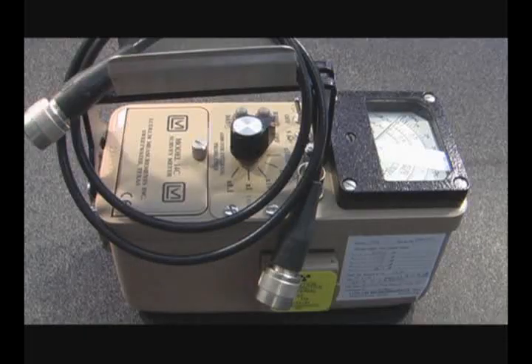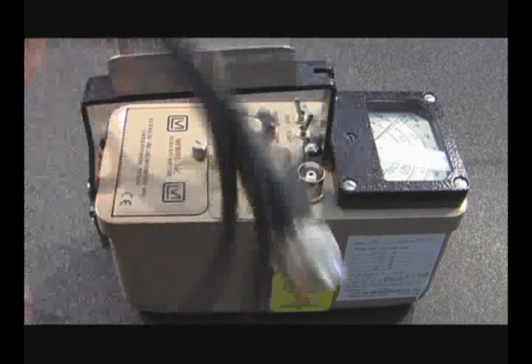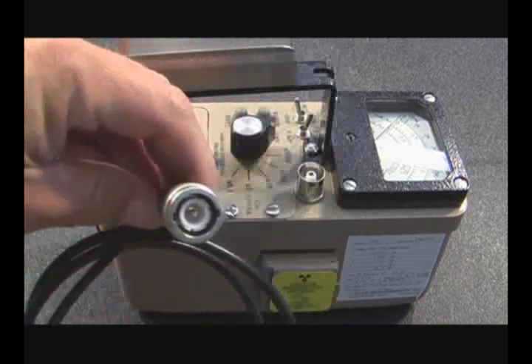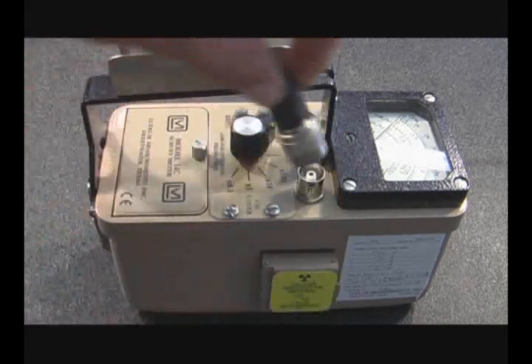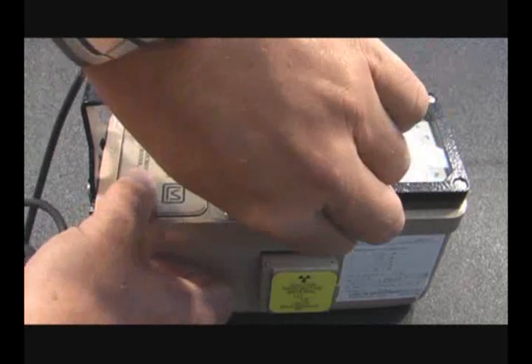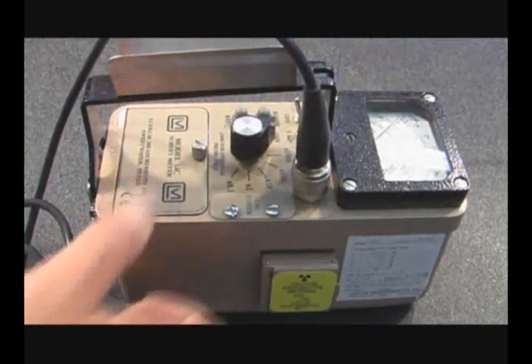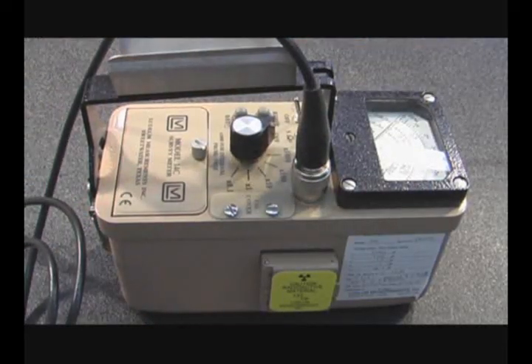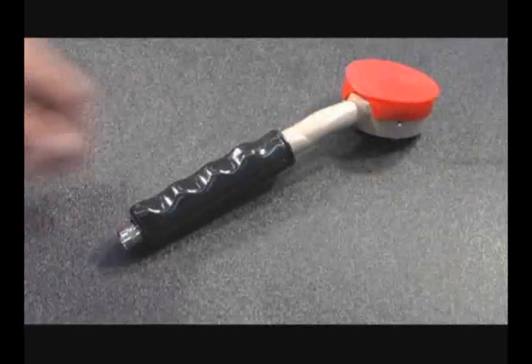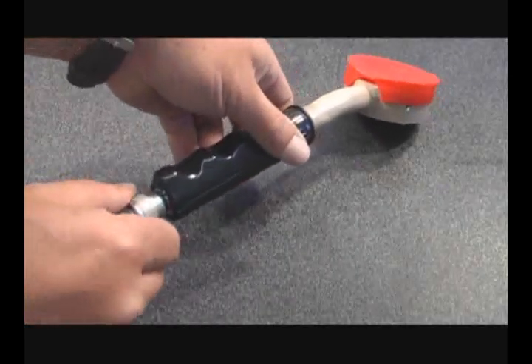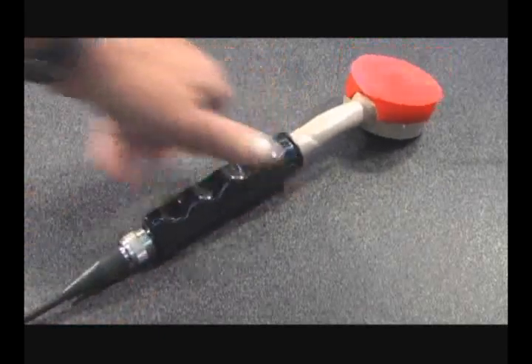The standard detector cable sent with each kit is made from coaxial cable with BNC-style connectors at each end. Connect one end of the detector cable to the instrument by firmly pushing the connectors together while twisting clockwise 1/4 turn until it latches. Repeat the process in the same manner with the other end of the cable at the Ludlum Model 44-9 detector.